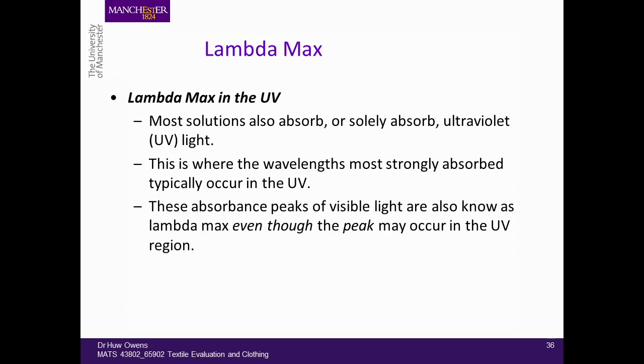As I said before, a lot of natural dyes will have their peak absorbance values outside the visible range, usually towards the ultraviolet. So that's not uncommon, and that's why these instruments tend to be a little wider in their range. And you can also use these UV-Vis spectrophotometers to just do a small range of values. So we might be interested in 300 to 400 nanometers.